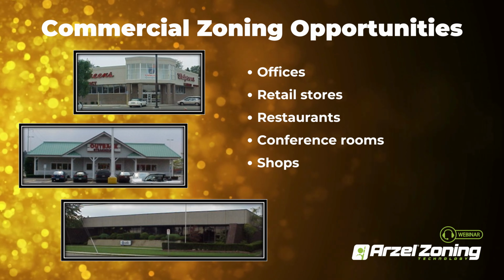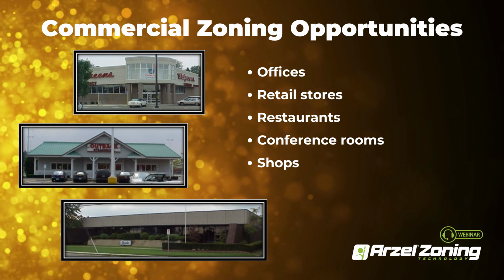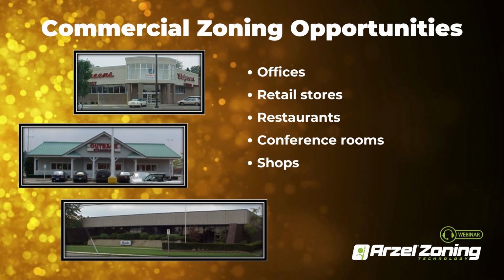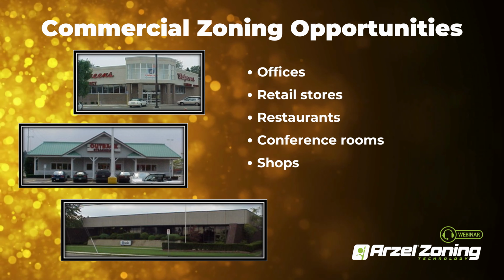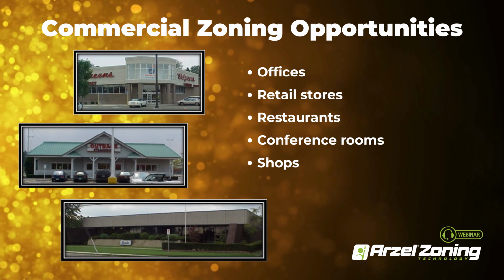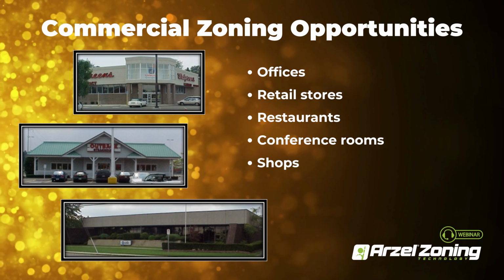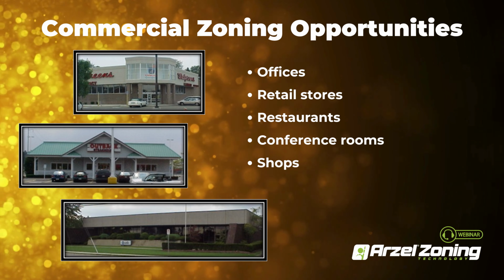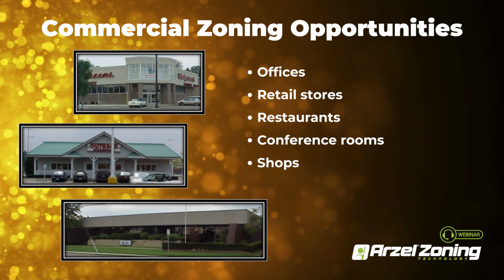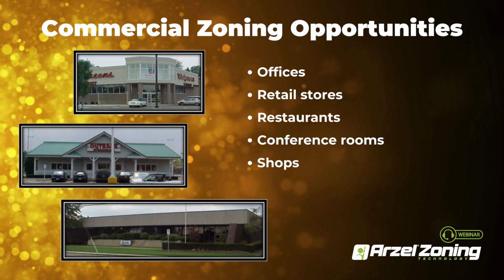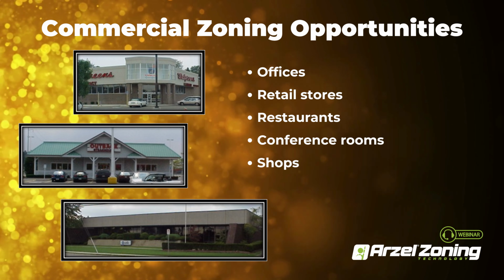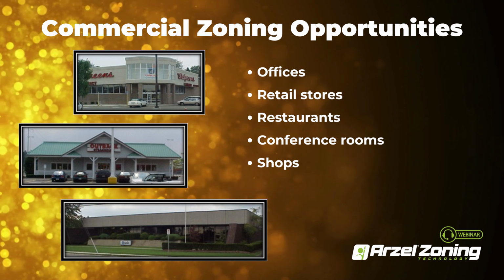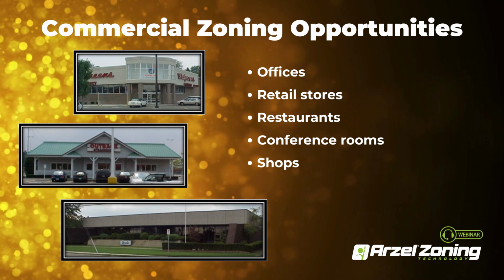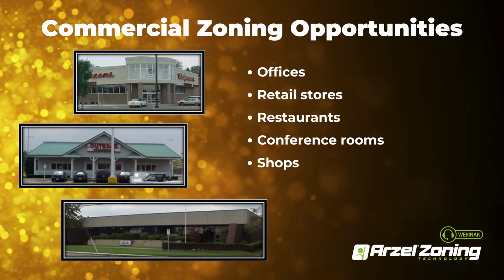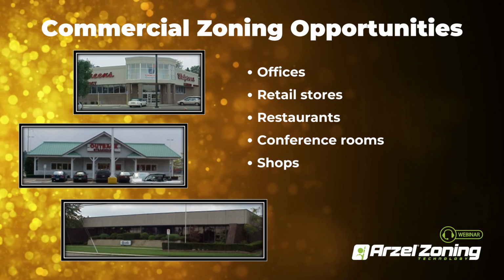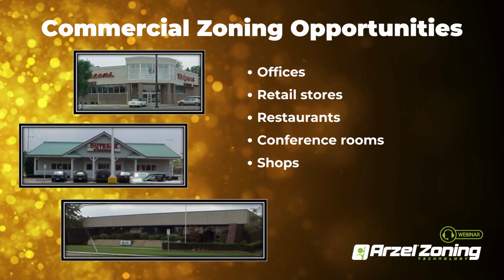And then you got your office space, so more commercial. How often do we have a situation where people on the glass exposure are complaining it's too hot in the summer months, while people in the center of the office without the glass exposure are complaining that it's too cold? You can split those offices up, give them probably 4 or 5 different zones of control - 2 areas in the glass, so north and south or east and west in the glass area, and then in the central part you can split it up to give them 2 zones as well, east and west, or however you have that conversation with your customer and determine what's going to best satisfy their needs. Those are all doable. Those are all easily achieved. It's just conversations that we have to determine what it is our customers are looking for.